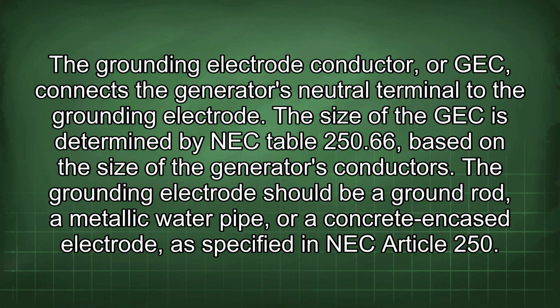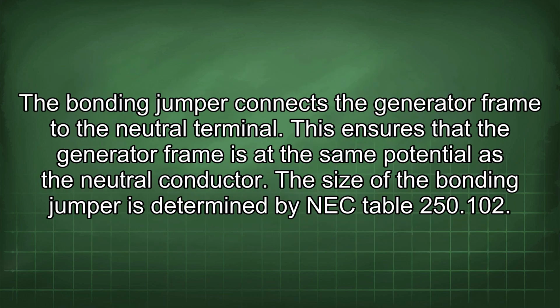The grounding electrode should be a ground rod, a metallic water pipe, or a concrete encased electrode, as specified in NEC Article 250. The bonding jumper connects the generator frame to the neutral terminal. This ensures that the generator frame is at the same potential as the neutral conductor. The size of the bonding jumper is determined by NEC Table 250.102.